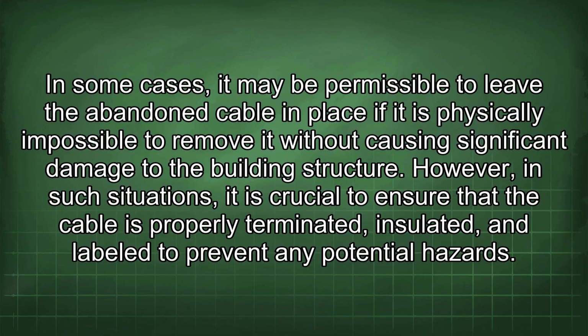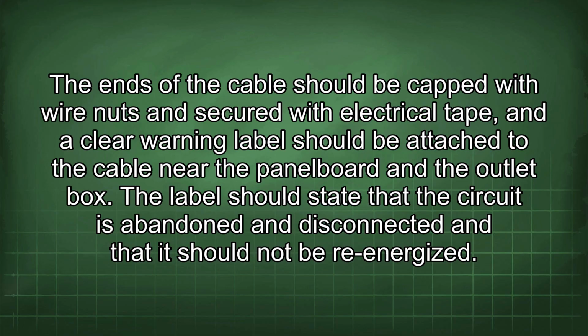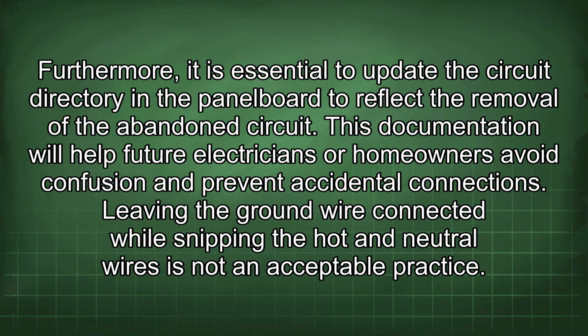However, in such situations, it is crucial to ensure that the cable is properly terminated, insulated, and labeled to prevent any potential hazards. The ends of the cable should be capped with wire nuts and secured with electrical tape, and a clear warning label should be attached to the cable near the panel board and the outlet box. The label should state that the circuit is abandoned and disconnected and that it should not be re-energized. Furthermore, it is essential to update the circuit directory in the panel board to reflect the removal of the abandoned circuit. This documentation will help future electricians or homeowners avoid confusion and prevent accidental connections.